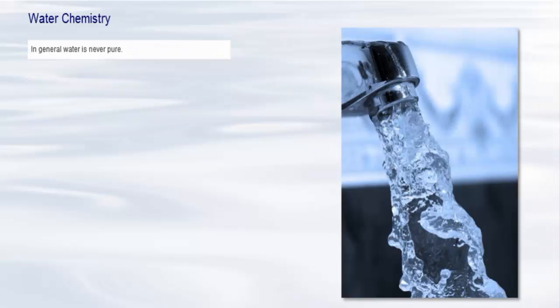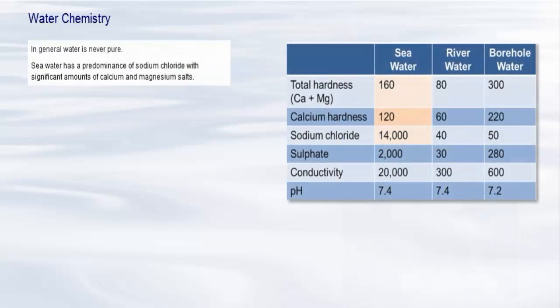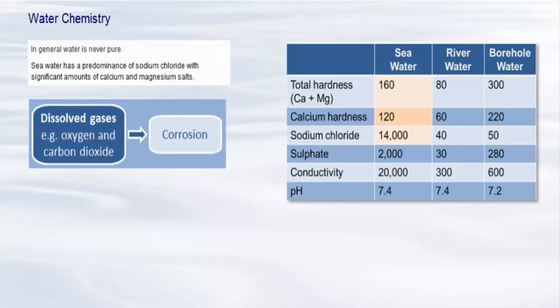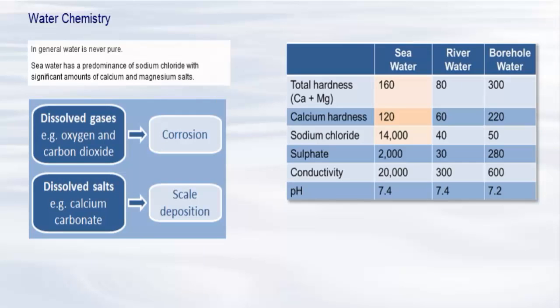In general, water is never pure. Normal tap water contains a number of constituents that are important and beneficial to our constitution. The table shows that seawater has a predominance of sodium chloride with significant amounts of calcium and magnesium salts. When introduced to marine steam boilers or engine cooling systems, these constituents will cause operational problems if not removed. For example, dissolved gases such as oxygen and carbon dioxide will cause corrosion, and dissolved salts such as calcium carbonate will lead to scale deposition. As we will see, corrosion and scaling are serious problems if not controlled.